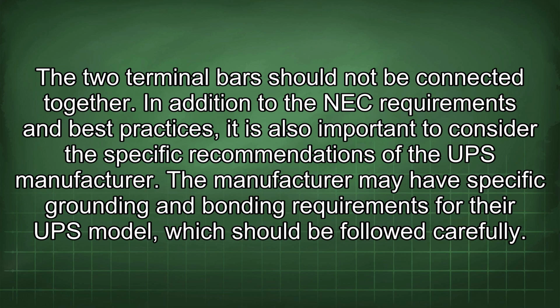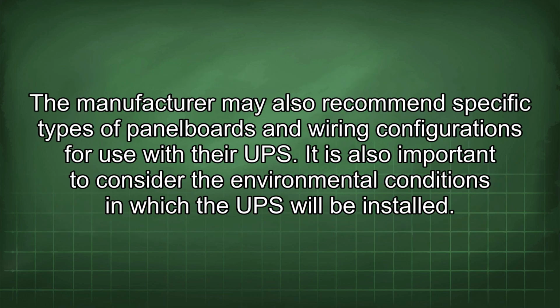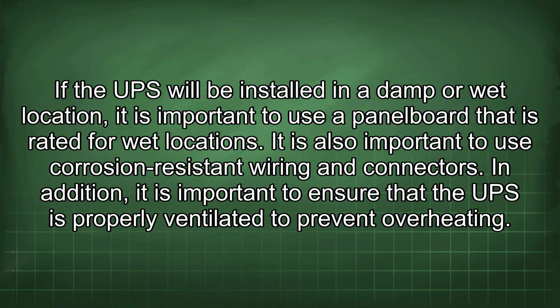In addition to the NEC requirements and best practices, it is also important to consider the specific recommendations of the UPS manufacturer. The manufacturer may have specific grounding and bonding requirements for their UPS model, which should be followed carefully. The manufacturer may also recommend specific types of panel boards and wiring configurations for use with their UPS. It is also important to consider the environmental conditions in which the UPS will be installed. If the UPS will be installed in a damp or wet location, it is important to use a panel board that is rated for wet locations. It is also important to use corrosion-resistant wiring and connectors.